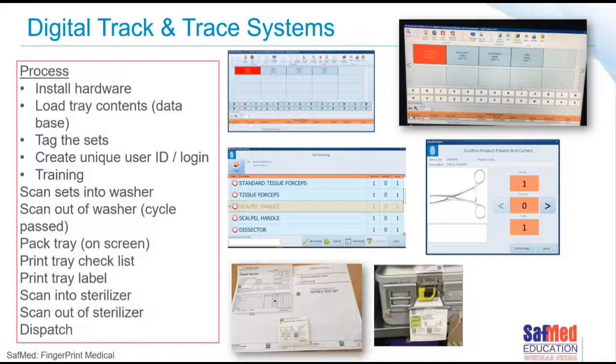End of the sterilization cycle. I can then again check my process challenge device, and I scan all of those items out of the autoclave again. If there's a decision in the dispatch area that you want to record, where everything is going also depends on your circumstances. Does it come straight out of the sterilizer to a storeroom that's only in the CSSD, or have you got a storeroom that's in the theatre, or wherever it is? You can now decide.